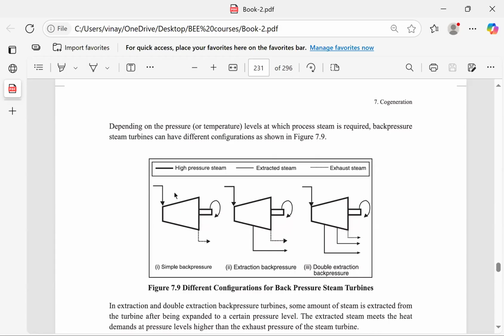Here, in this first case, the pressure and temperature of the steam is fixed. In this case, I have two pressures and temperatures of steam available. If the requirement of the process is only 5 kg, I will get 5 kg steam here. If it is say 25 kg, I will tap it from this point and use 25 kg.